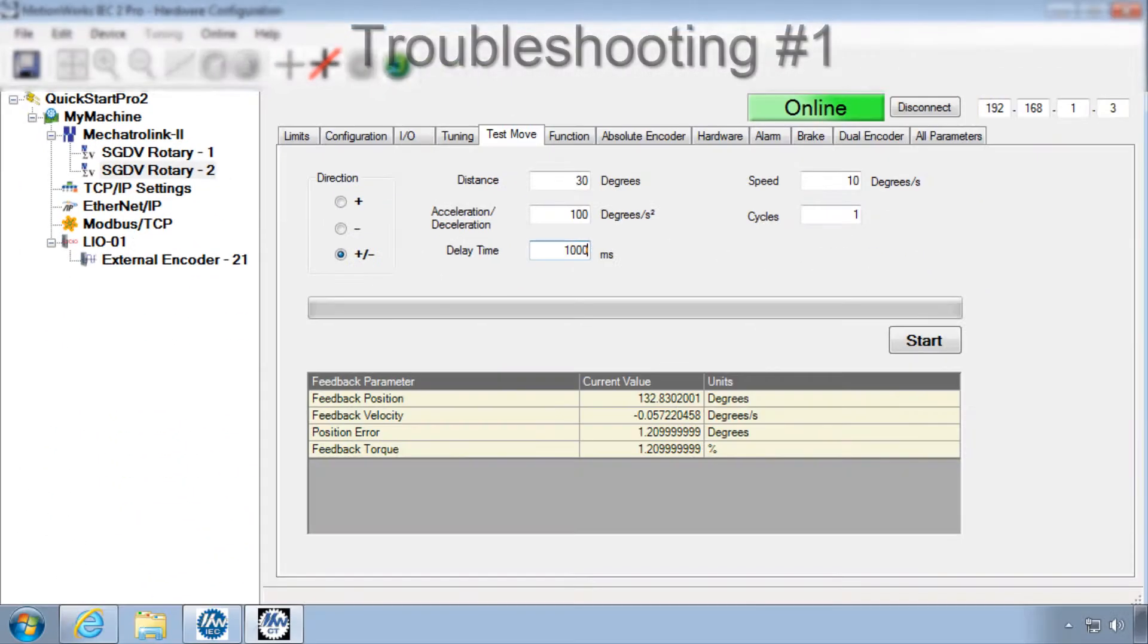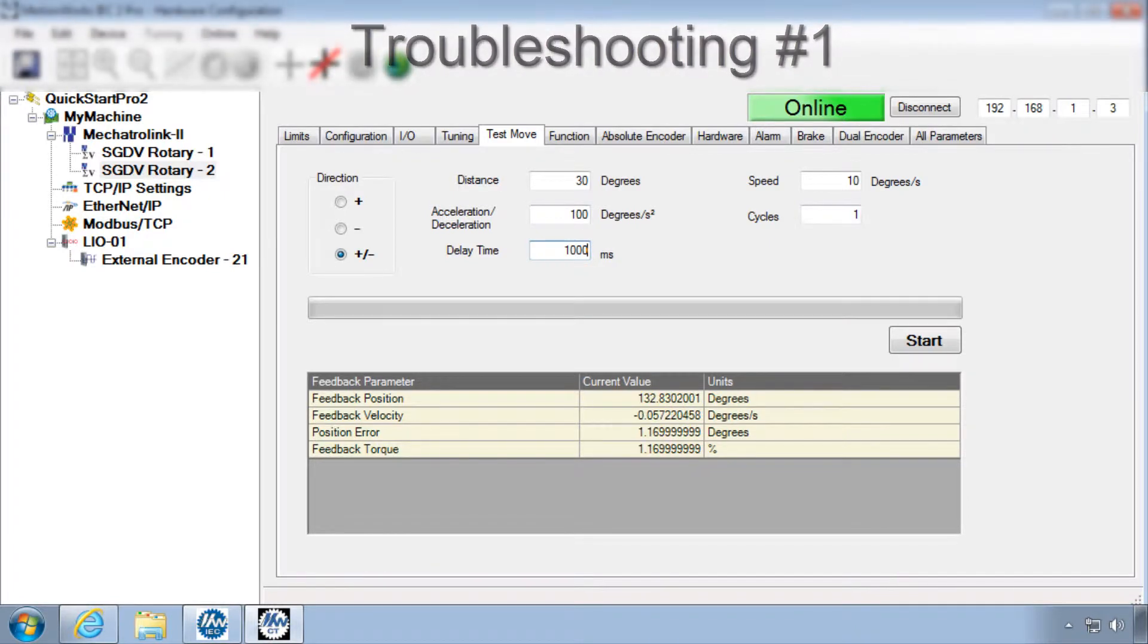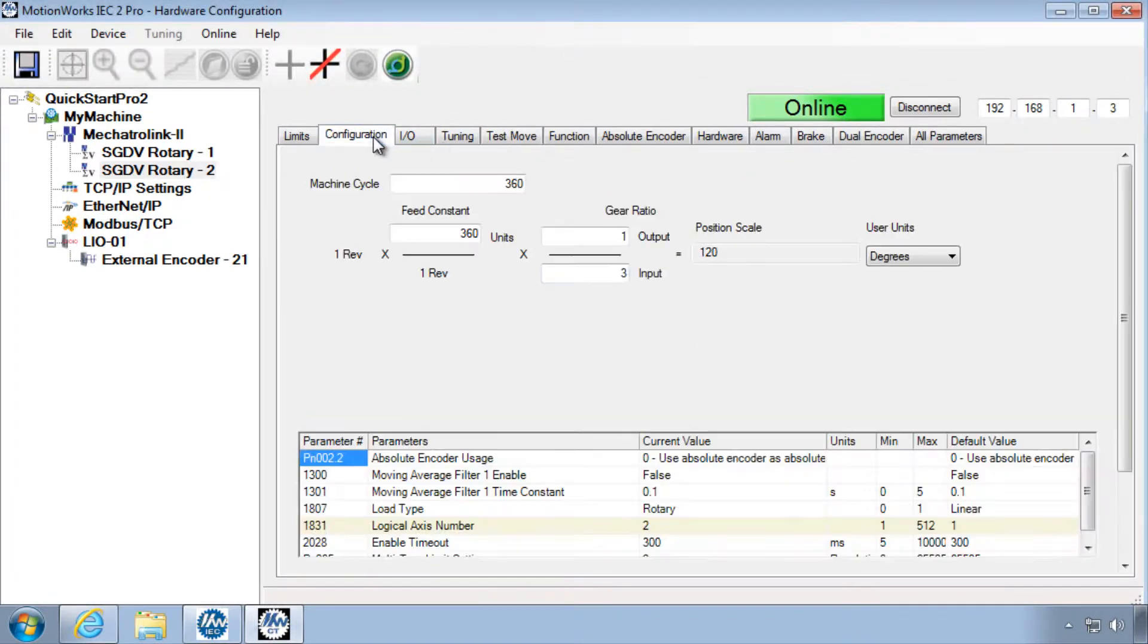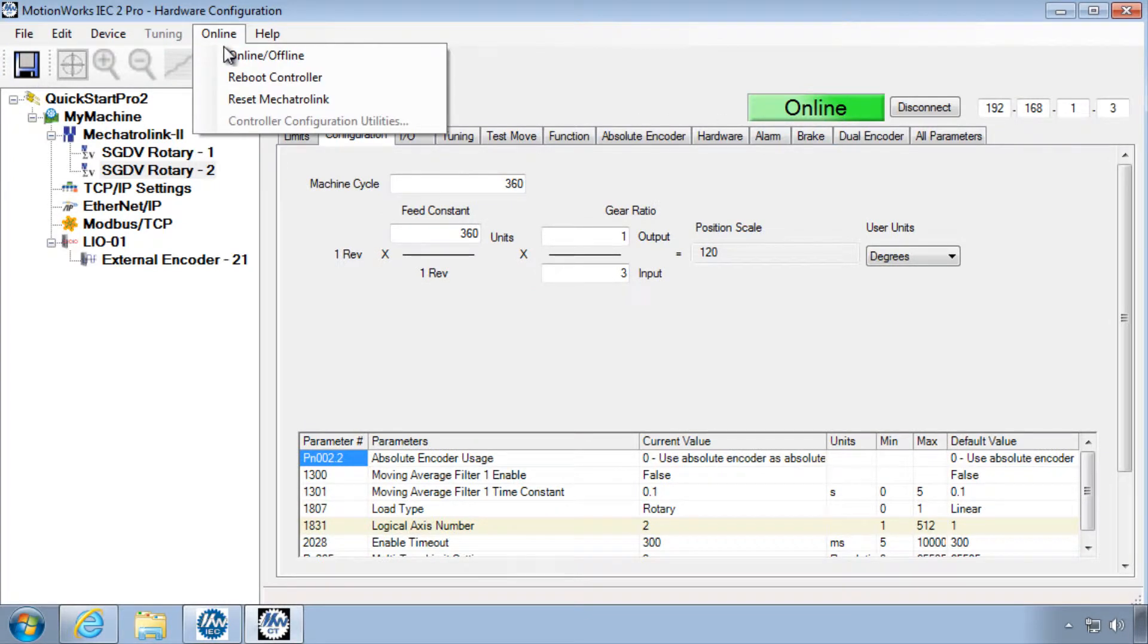If test move is not moving the distance and speed expected, you want to go back and check the configuration tab and save while you're online, and then under online, reboot the controller. The most common reasons for an incorrect test move are either saving offline instead of online, or not rebooting after the online save.